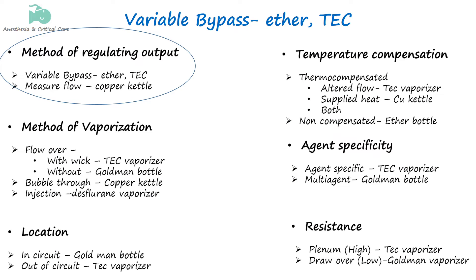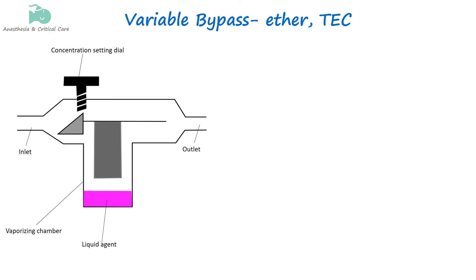We will start our discussion with the methods used in vaporizers to regulate their output. It includes variable bypass and measured flow. The variable bypass system consists of an inlet, an outlet, and the vaporizing chamber.